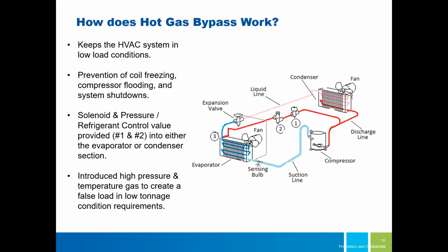So basically the evaporator looks as if it's fully loaded, and you can see, well, hey, if I'm dumping hot gas into it, that's what it is going to kind of think, right? Because it's going to run really hard when it thinks it needs to. And I actually incorrectly put something on the slide here. It's supposed to keep the HVAC system out of low load conditions.